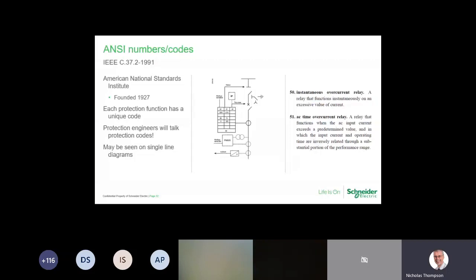Now, all protection relays work on protection functionality, and all protection functions will have a particular code against them. The origin of these goes back to 1927 and 1928 with the American National Standards. American National Standards basically are within the ANSI-NEMA area of the world, but it seems to be a method of determining what protection you want for that particular circuit breaker. So there's a set of unique numbers or codes. There is also going to be a series of letters as well, and sometimes you combine the numbers with the letters to give you a protection functionality.